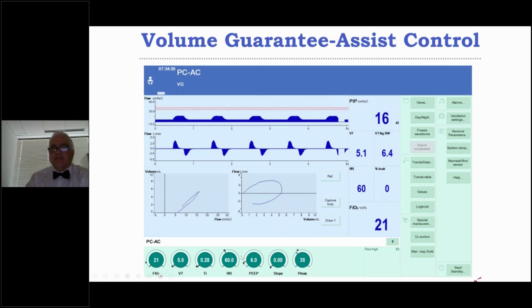Now, look here at what's happening. Again, it's not evident from the scalars, but if you look at the loop here, this loop doesn't return to zero. So this baby may be going a little bit fast for that mode of ventilation. Because you don't have a scalloping here, this may also reflect tube leak. Although, again, when you look here, your tube leak is 0. So be very mindful of what can happen with any of these modes and be able to distinguish these and be able to understand where you are.